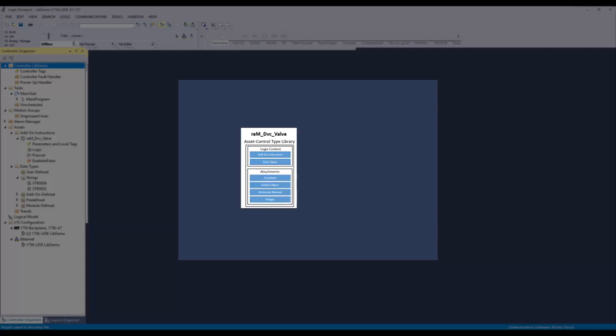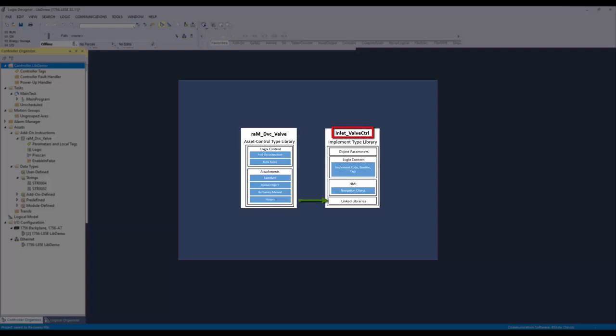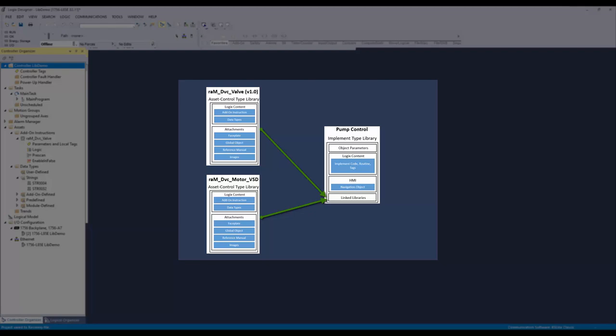Having separate asset and implement type libraries gives freedom to the user to create their own implement library to suit requirements. The user can create an implement type library linked to a single or many assets. While updating contents like addon instruction or faceplate, the user only needs to update the asset type library. The implement library remains unchanged and gets the updated addon instruction or faceplate from the asset library.